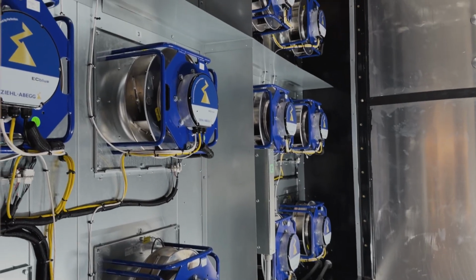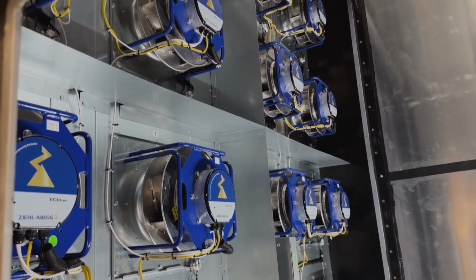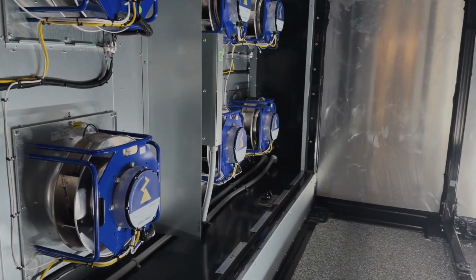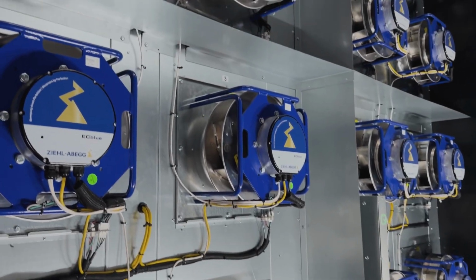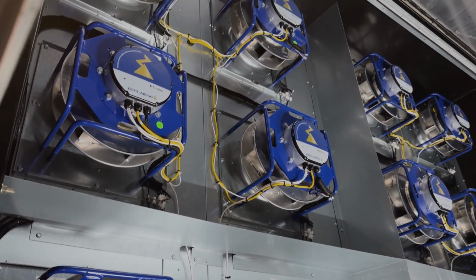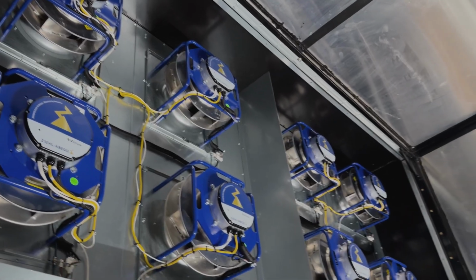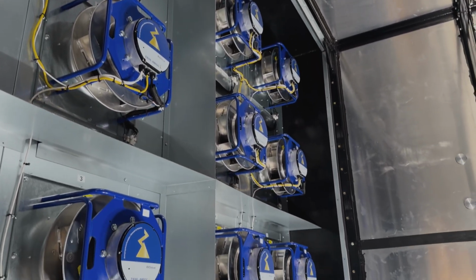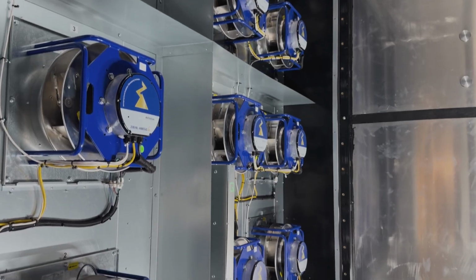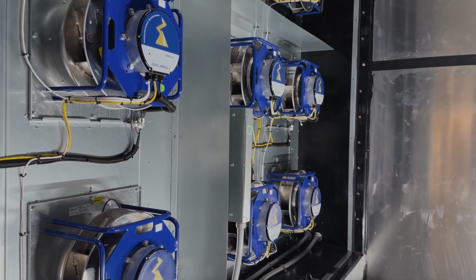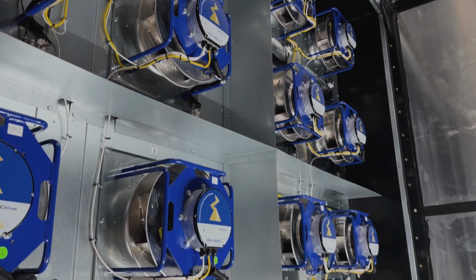Do you have the same amount of layers on that side as you did on the other? We actually spec'd 3 layers on this originally. It turned out that we got better airflow with just 2 layers of diffusers here. So we just have 2 here. We have the capability to add that if we ever change something in our flow regime. For instance, if we changed out our supply fan for some customer's air handler, and that changed the flow coming into the screens, maybe we'd change out the screens for that. A very unique feature of this airflow tunnel is that this fan unit is modular. It can be pulled away, and we can substitute any other equipment in here.